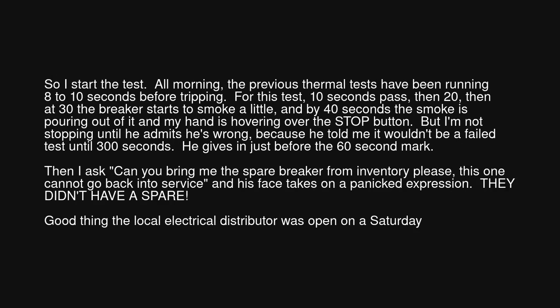So I start the test. All morning the previous thermal tests have been running 8 to 10 seconds before tripping. For this test, 10 seconds pass, then 20. Then at 30 the breaker starts to smoke a little. And by 40 seconds the smoke is pouring out of it and my hand is hovering over the stop button. But I'm not stopping until he admits he's wrong. Because he told me it wouldn't be a failed test until 300 seconds. He gives in just before the 60-second mark. Then I ask, can you bring me the spare breaker from inventory please? This one cannot go back into service, and his face takes on a panicked expression. They didn't have a spare. Good thing the local electrical distributor was open on a Saturday.